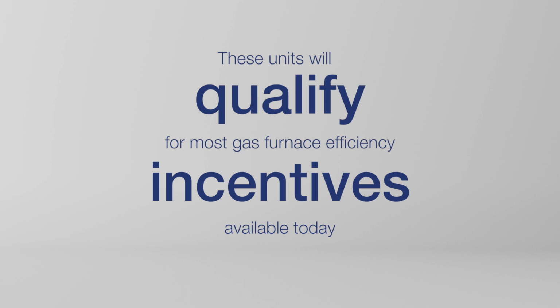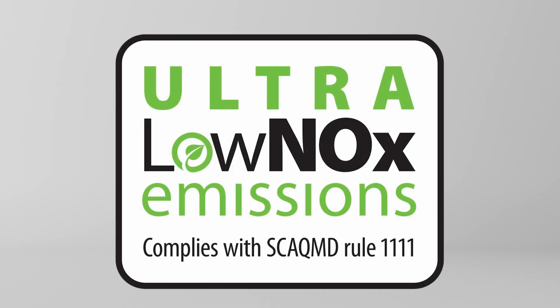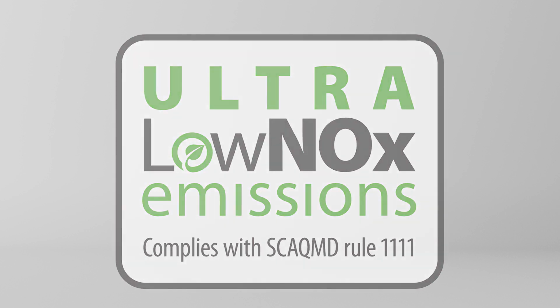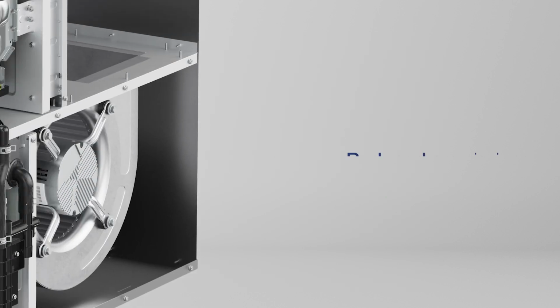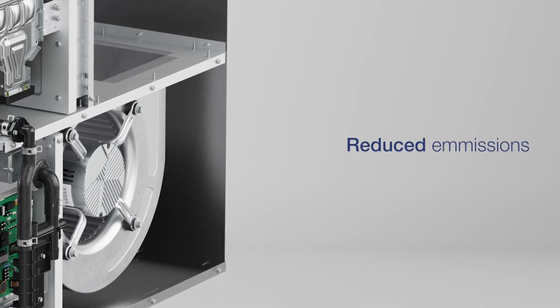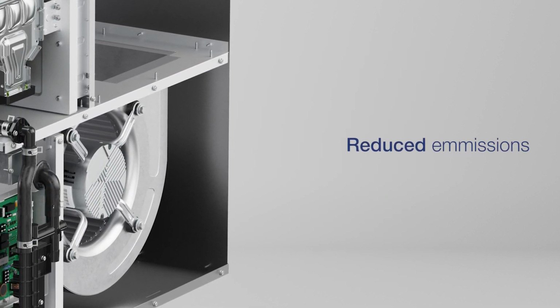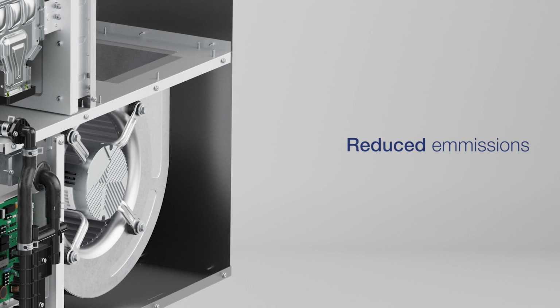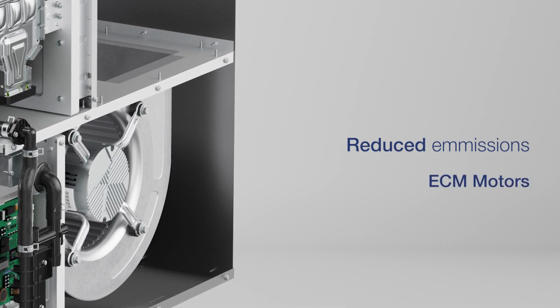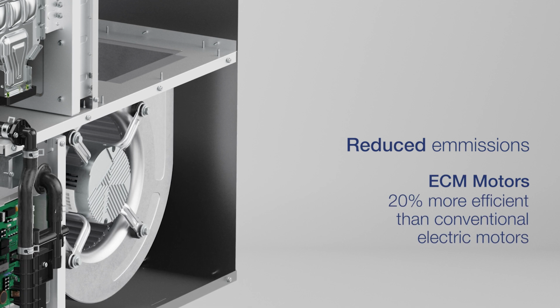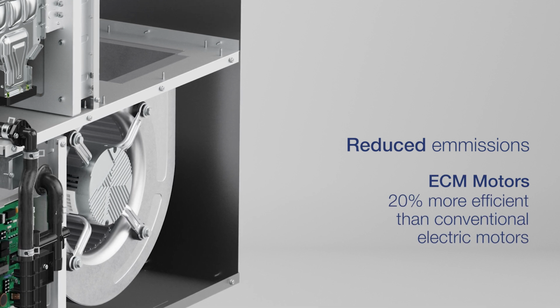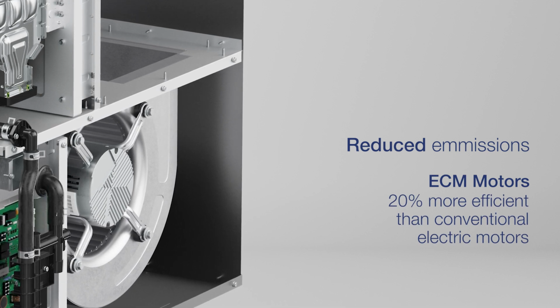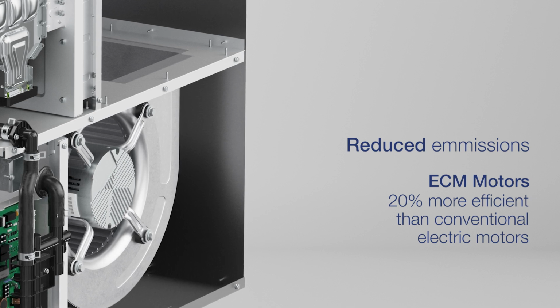The NPF is a great green story as well. As we said, the NPF is 97% efficient, so it makes excellent use of our natural gas resources while meeting stringent ultra-low NOx requirements. Now, these reduced emissions can also lead to less acid rain and smog. Couple all that with ECM motors that are typically at least 20% more efficient than conventional motors, and you have a product that's a steward for both natural resources and for the environment as well.